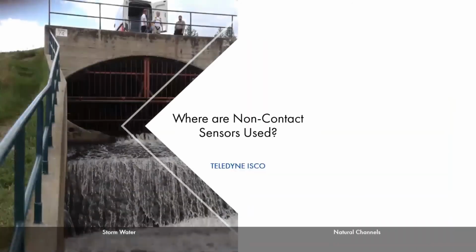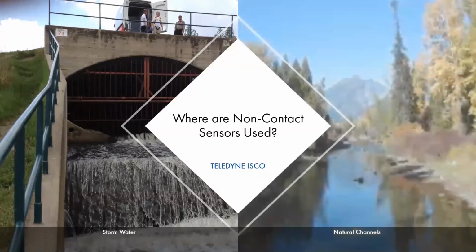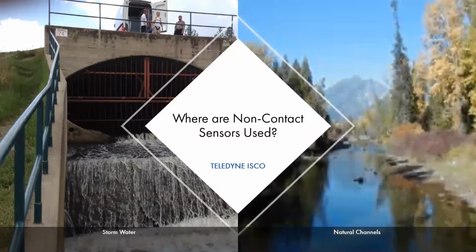So where are the non-contact sensors used? You can use them in stormwater applications, which they're ideal for because you don't know what kind of debris is going to go through there: shopping carts, trees, anything. That would potentially tear out an in-pipe sensor. So having it above the flow stream is going to save you time and money. You can also mount them on natural channels, rivers and streams.